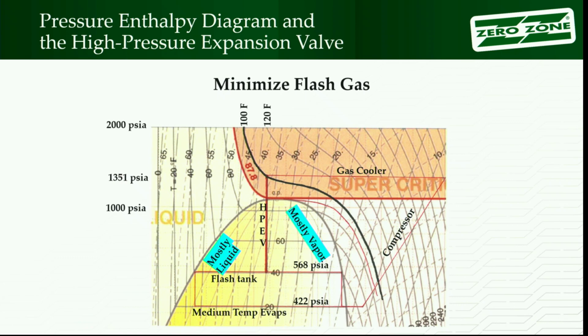Because you think of other things, you've got compressors. I said I've got VFDs. They're running on PIDs. And I've got all the expansion valves, they're running on PIDs. My flash gas valve is running on a PID. You've got all these things running around on there. If they get good information, the software has a better chance of giving you good results. So if you're having trouble with the system, not a lot of control, you might want to take a trip to the roof to see how that baby's hanging up there, if that high pressure valve's not moving around much.